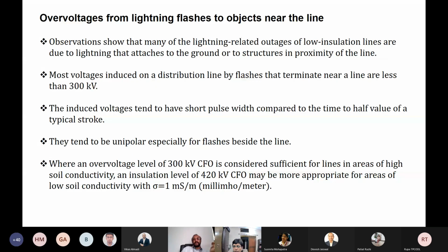Then where an overvoltage level of 300 kV CFO is considered sufficient for lines in an area of high soil resistivity, an insulation level of 420 kV CFO may be more appropriate for areas of low soil resistivity. What is the meaning of this? This is a very, very important point that many people forget. If the soil conductivity is less in a given area, the chances of flashover are high. I think I mentioned that in a previous slide as well. Therefore, in a high soil resistivity area, if you have a CFO of 300 kV, then in the low soil conductivity area, it should be like 420 kV.